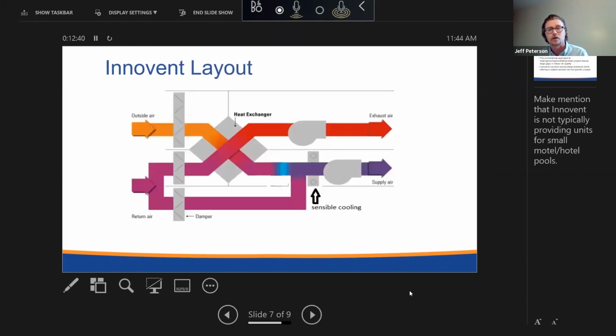So this is kind of what the airflow diagram looks like. Pretty simple and straightforward. A little different than, maybe, a 100% outside air ERU, but you've got your outside air entering there in the upper left, coming through in summer. That's going to be about 50% of the nominal supply CFM that we bring in through heat recovery, right? That higher outside air dew point, we need our maximum amount of that to offset the dehumidification load. So we bring it in through the plate heat exchanger, and then we mix it with the remainder of the return air from the pool that's not exhausted out the other side of the heat exchanger. And if it needs to be tempered at all, we can do a little trim with sensible cooling, get the supply condition to the right spot, and deliver it to the space.